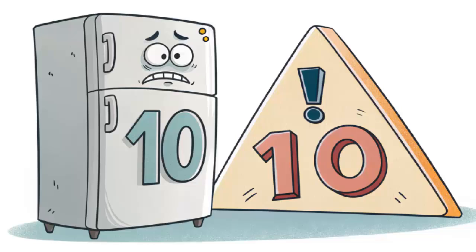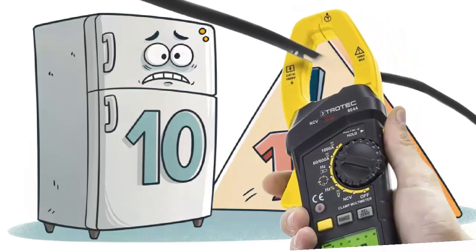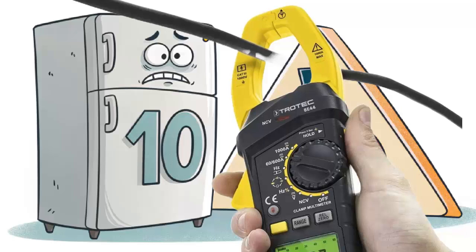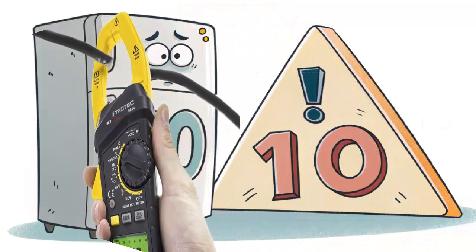3. Excessive current consumption. Measure the compressor's current draw with a clamp meter and compare it to the rating on its label. Pay attention to two values: RLA, running load amps, for normal operation and LRA, locked rotor amps, for startup.